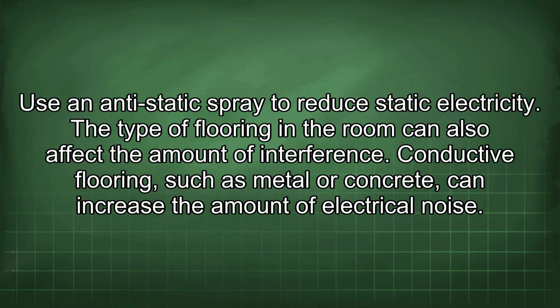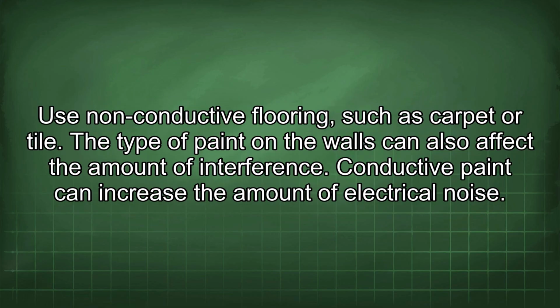The type of flooring in the room can also affect the amount of interference. Conductive flooring, such as metal or concrete, can increase the amount of electrical noise. Use non-conductive flooring, such as carpet or tile.